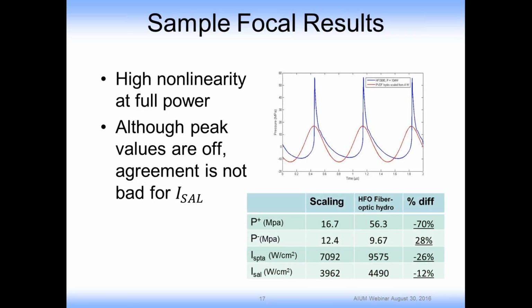So I want to give some example results. The blue curve here shows the result from the hydrophone, which actually also agrees with simulations, I should mention. So we have trust in this shape and form. Basically what you see is that in reality, in water, the waveform is distorted. You see a high amplitude positive pressure and the negative pressure is not so high. On the positive end, it's narrow. This is what is called a weak shock wave, effectively.